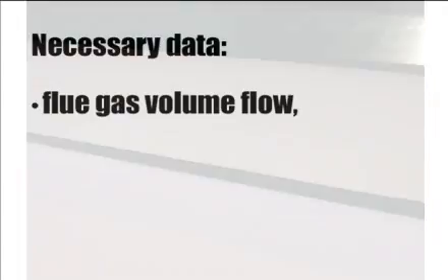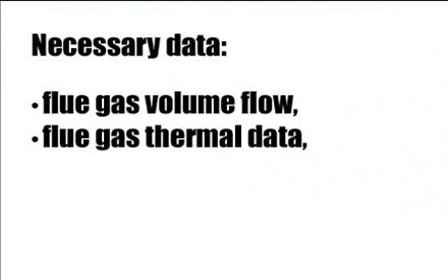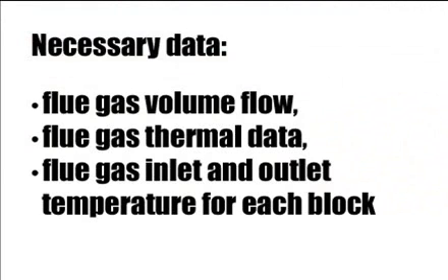However, what I definitely need is the thermal management calculation, which was done by my colleague specialized in such boilers. The calculation contains all necessary data we need: flue gas volume flow, thermal data of flue gas as a function of temperature, inlet and outlet temperatures of flue gas for each and every tube bundle.